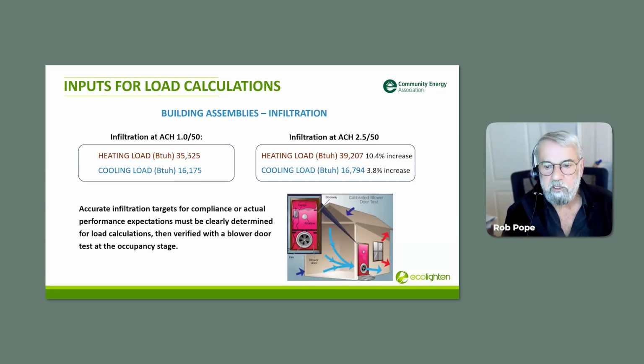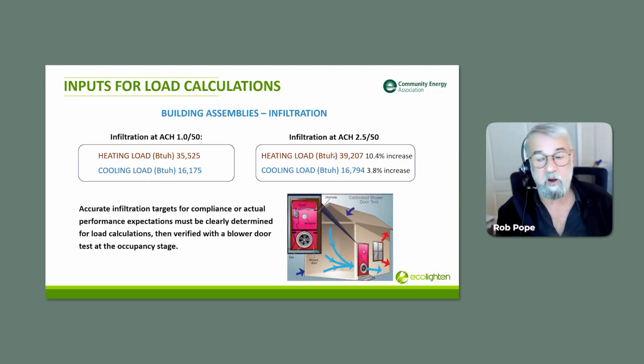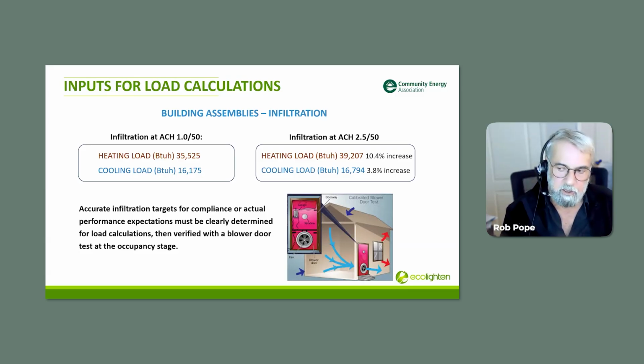Remember these numbers: 35,525 for heating, 16,175 for cooling. We changed it to 2.5, which is still good, but that increased the heating load by more than 10%. In this case, to address the question we had before—would we go up to the next size or keep it at 3 tons—I'd be a little more cautious about keeping it at a 3-ton system. I'd be a lot more comfortable going up to a 3.5. Or depending on the manufacturer, they might not have half-ton increments—you might have to go up to 4 tons, but in that case it'd have to be variable.